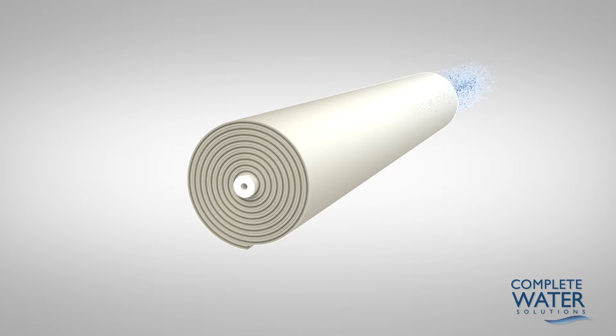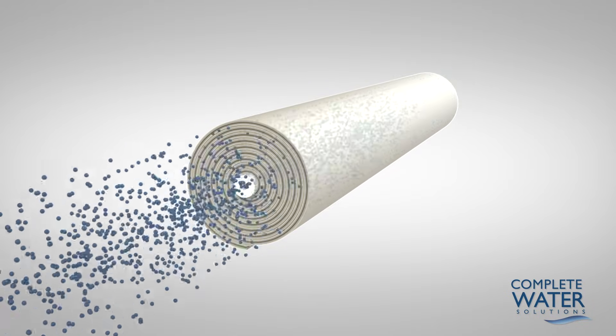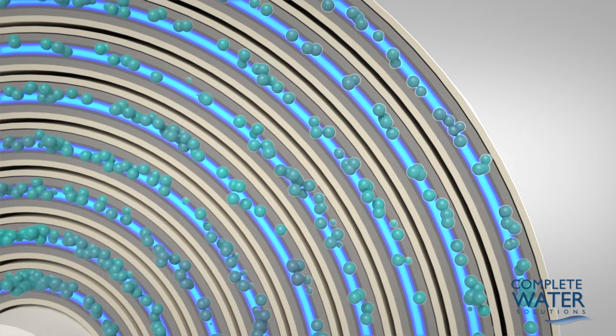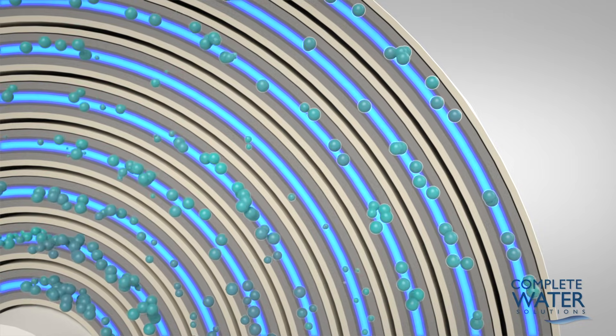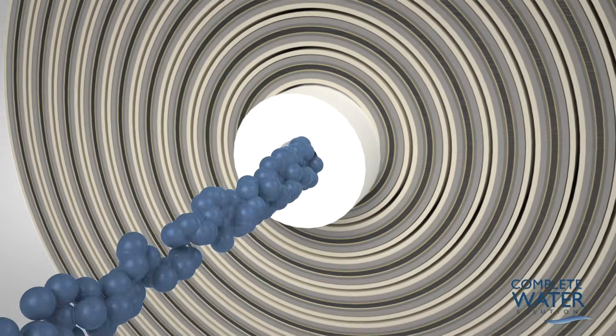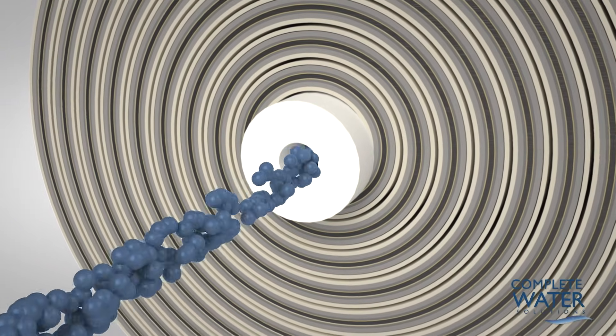Feed water is forced through the feed channel spacer and into the barrier layer of the membrane. Water passes through the membrane surface into the permeate channel. It flows in a spiral direction and collects in the core tube. This water is the final reverse osmosis water or permeate.